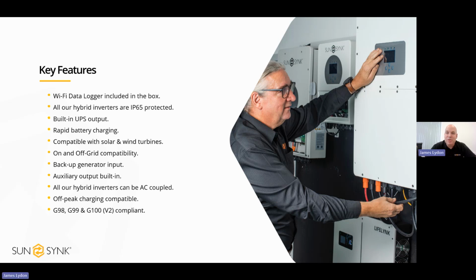Backup generator input. If someone is completely off grid, unless it is a garden bar or something like that, most of the time people will want some sort of redundancy power, and that is always in the form of a backup genny. We have a dedicated input on the bottom of the inverter for a backup generator, and if that backup generator supports ATS, the auto start signal, our inverter can control that backup generator.